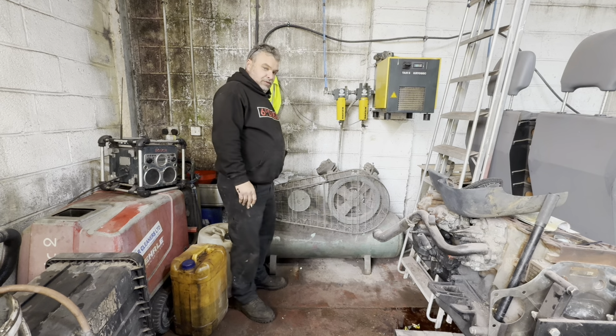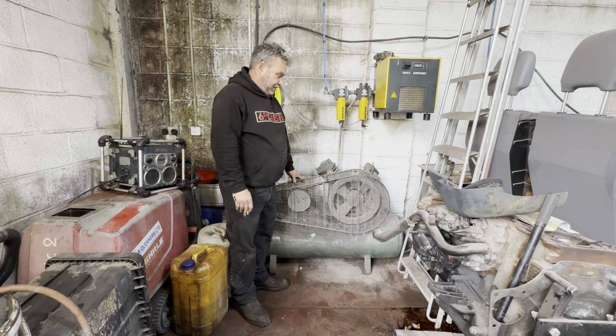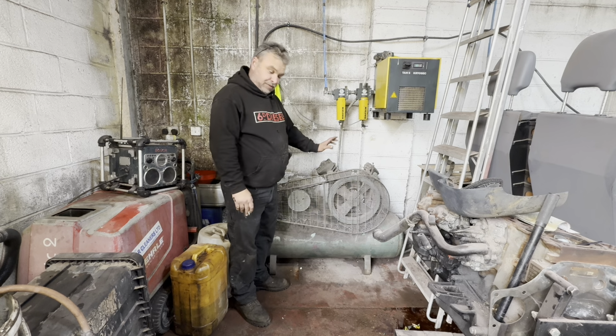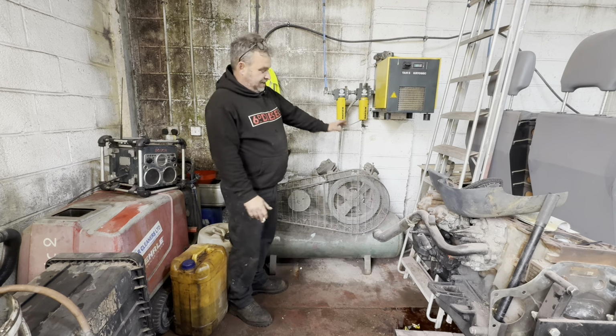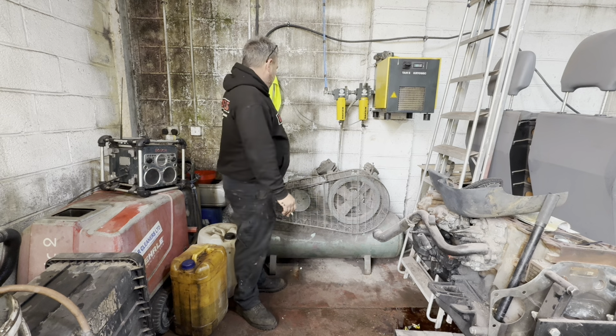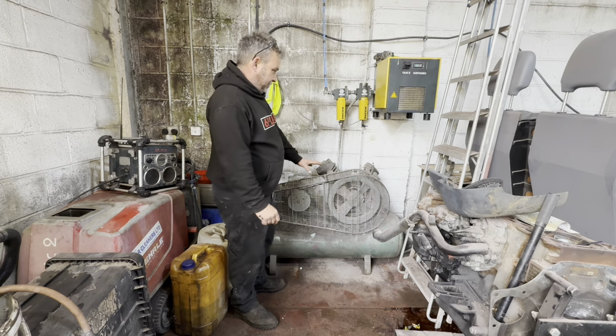So when it all went to hell, we very, very quickly, Dom had disabled the auto start on this. So the auto start is the fact that when this shuts down, when it's up to pressure, originally it would have clicked back in again as soon as the pressure dropped, and then it starts chuddering away and building air. But we turned that off because it's in the same loop technically as the other compressor outside, and you didn't need 2 running. So I've fixed that. I figured out what Dom did, so it's now back auto starting.